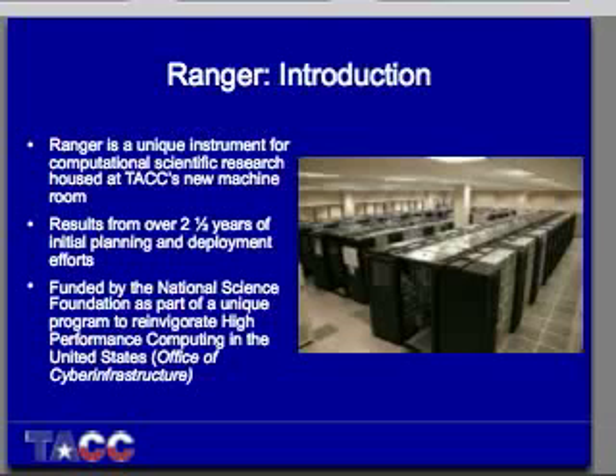Between the C48 Constellation racks, we're using APC in-row heat exchangers, which carry about 90 to 95% of the heat load of the entire system. That's why it's enclosed from the top—you want to get all that hot air into the heat exchanger so it can be very efficient.